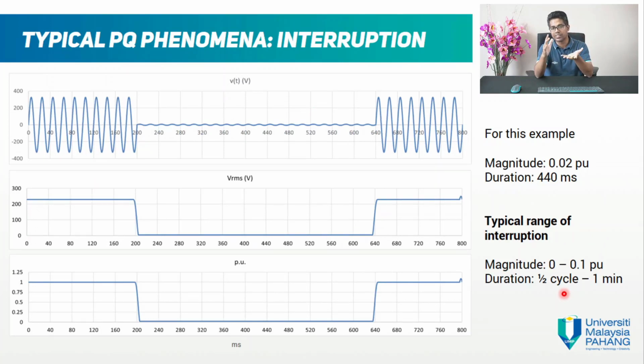Interruption is different from voltage sag. Voltage sag is from 0.1 to 0.9, but when it goes below 0.1, this is what we call interruption. Okay, you might experience this. You call this event a blackout. Okay, but that's not the term that we will use in this course. It's called interruption. Power interruption. Normally, all electric loads will fail in this kind of problem, unless you have a backup like a UPS. Okay, so this typical interruption is at 0.02 pu and at 440 milliseconds. Okay, duration can last for half cycle to 1 minute as well, and at 0 to 0.1 pu.